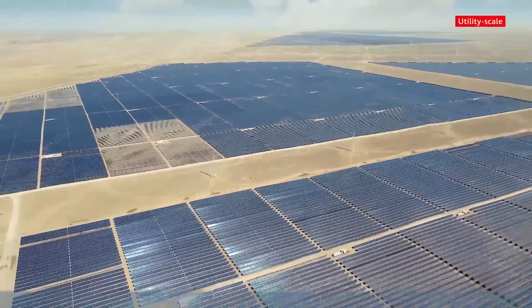And this one up here is an industrial computer that collects and takes measurements such as voltage and currents. We have fuse holders for the PLC and voltage transformer measurement, enabling the voltage measurement of the STS. And we have here the main MCCB of auxiliary services, which from here takes the 800V AC and sends them to the transformer we saw in the medium voltage side.